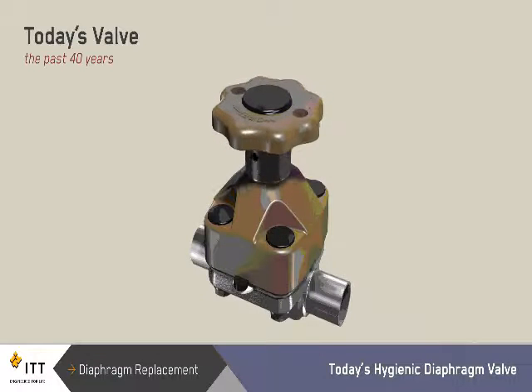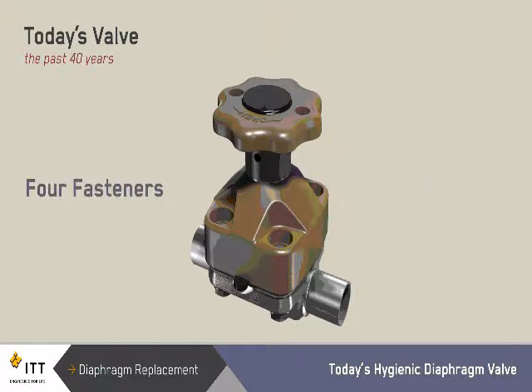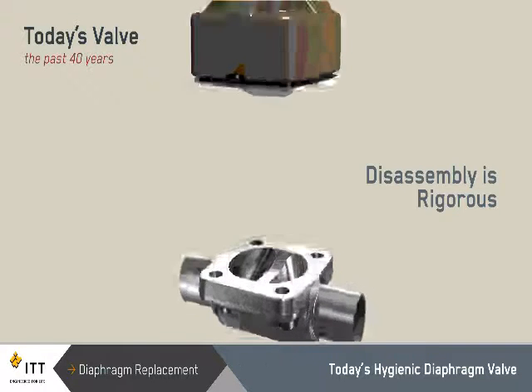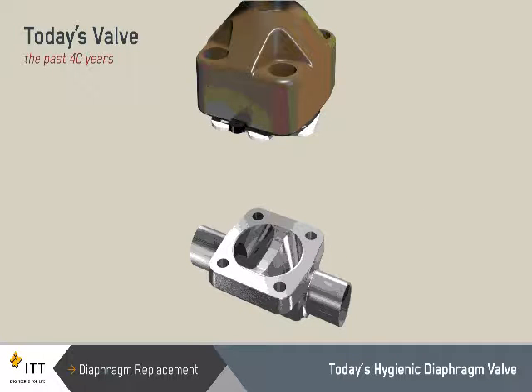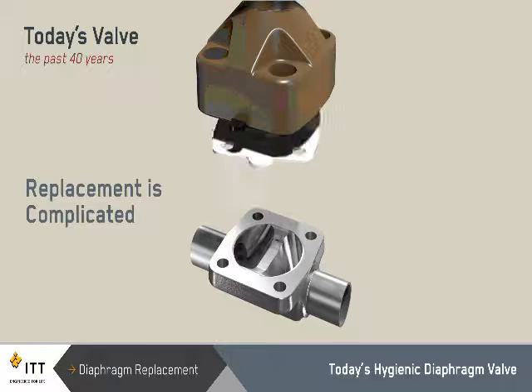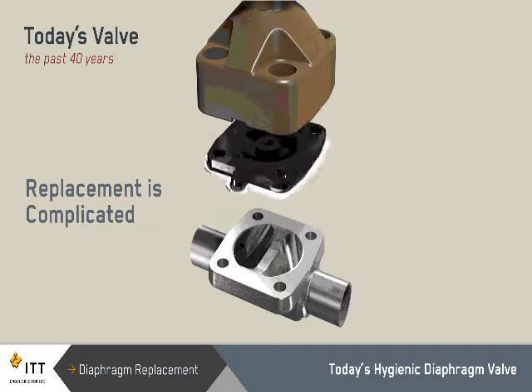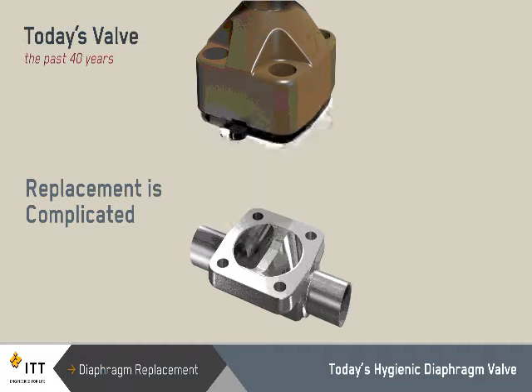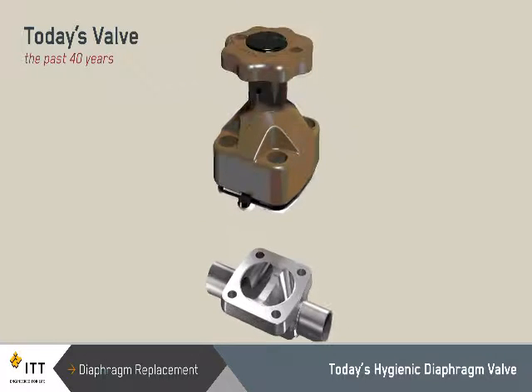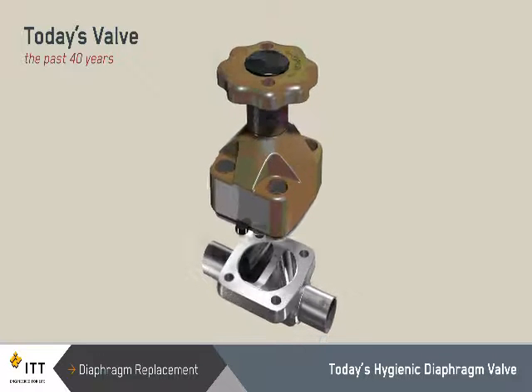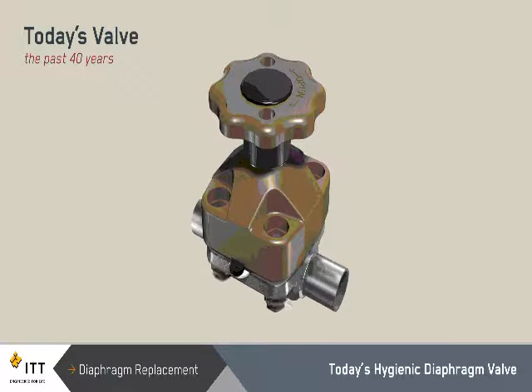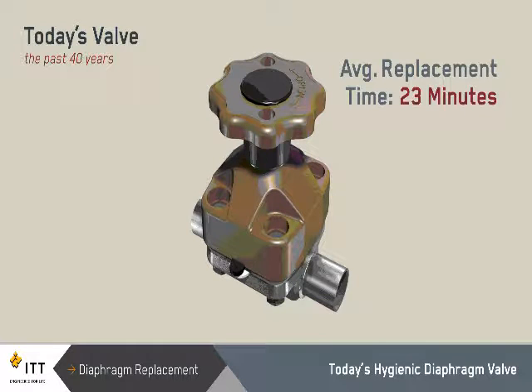Today's hygienic diaphragm valves use 4 fasteners to connect the valve body, diaphragm, and topworks. The valve disassembly process is rigorous, and care must be taken when removing and replacing fasteners. Often, diaphragm replacement is complicated by valves that are installed in hard-to-reach locations with limited access. Maintenance professionals in the biopharm industry have confirmed that the average time to replace the diaphragm in today's valve design is approximately 23 minutes.